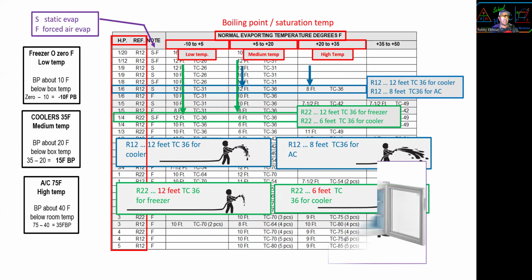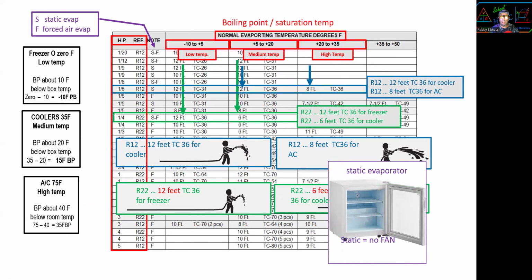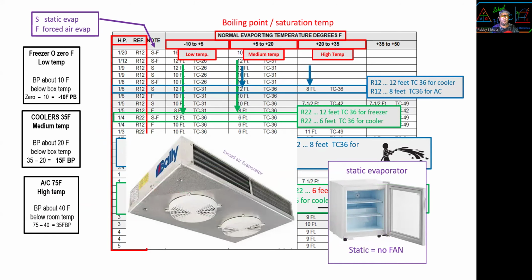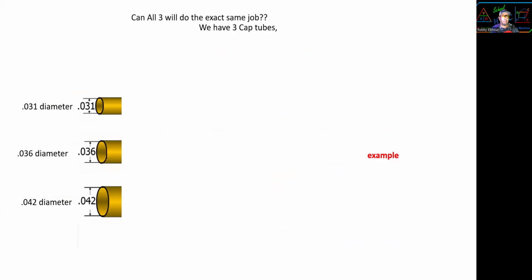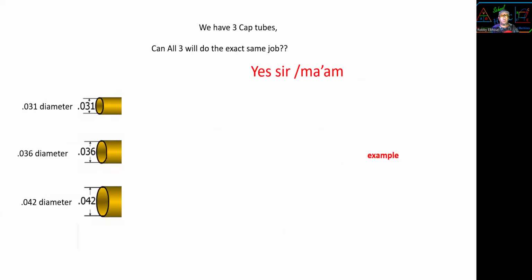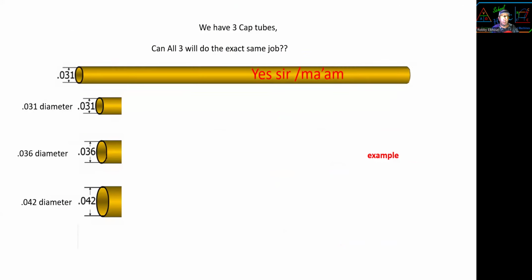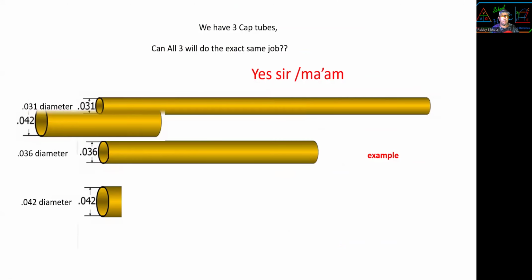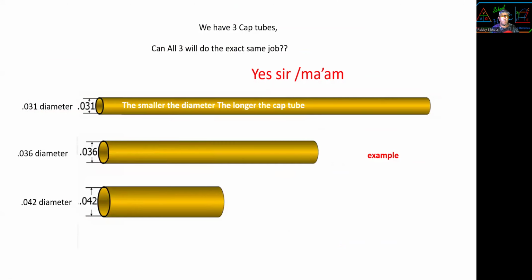Now, next, the note, static versus forced air. That's your static evaporator, no fan. Static equals no fan. Forced air equals forced fan. We have 3 cap tube diameters. Can all 3 do the exact same job? Yes, sir, ma'am. Longer, medium size, and short. The smaller the diameter, the longer the cap tube. The larger the diameter, the shorter the cap tube. The diameter and the length affect pressure drop.